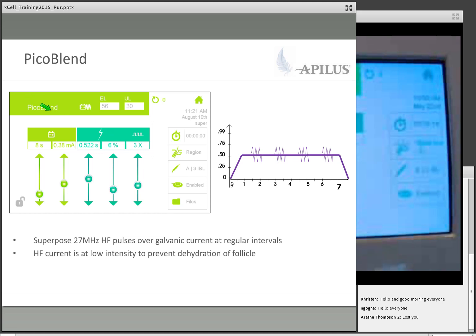And because the Pico blend is a pulsing blend, we have pulses here. So when we look at this screen, we have an 8-second pulse at 0.38 mA, and then we have 3 pulses of high frequency in that are about half a second each at only 6% intensity. So when we look at a graph, the trapezoid shape here is the galvanic.